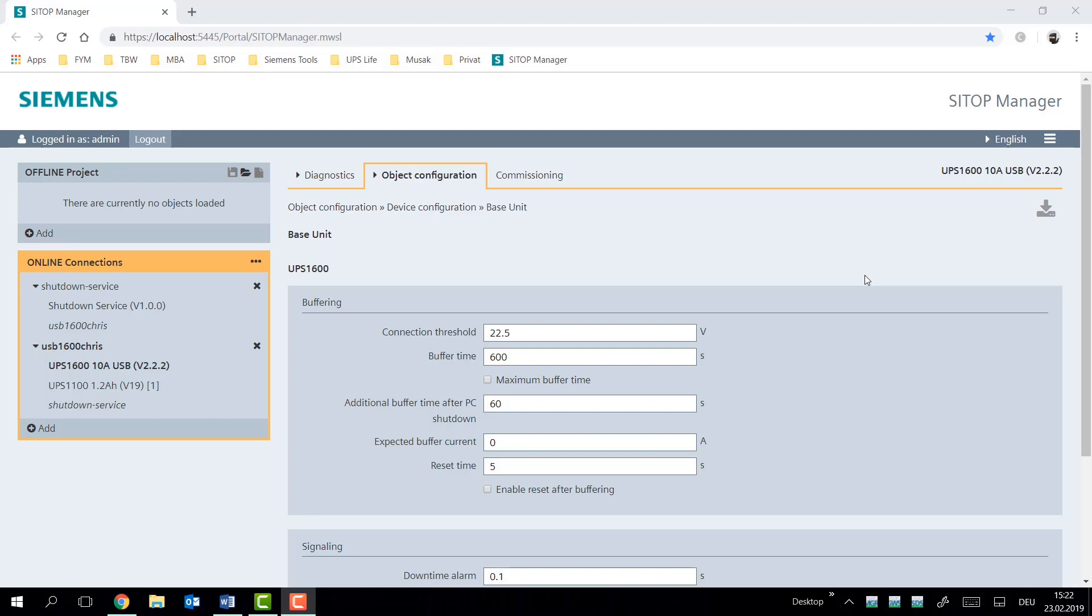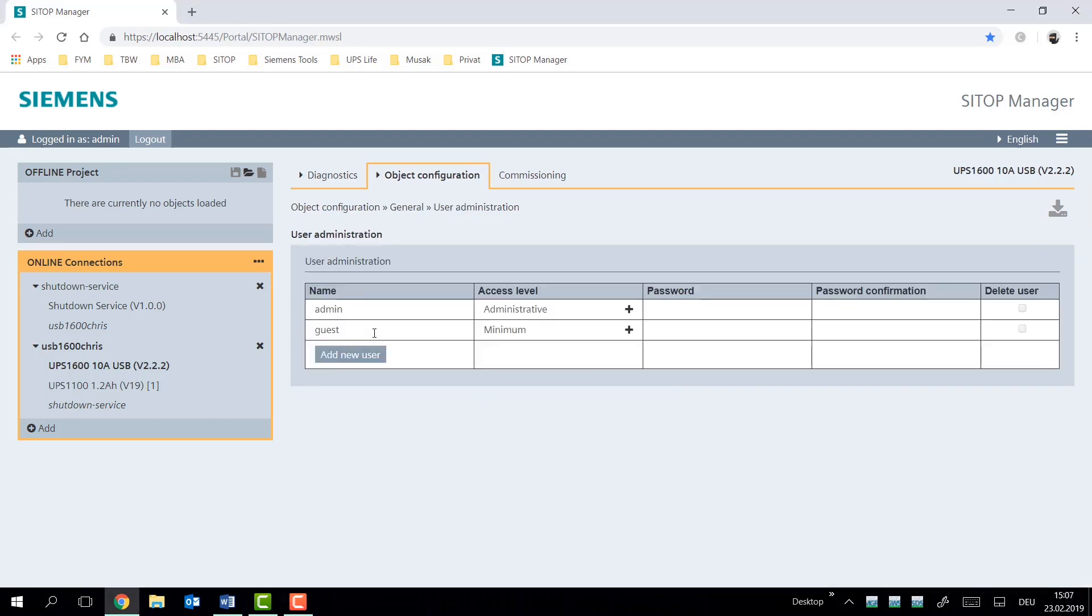The connection threshold here at 22.5 volts represents the minimum voltage allowed by the UPS1600 in your network. Any voltage variations above 22.5 volts will not be buffered. The moment that the voltage drops below 22.5 volts, a buffer event will be signaled and the UPS will switch to buffering mode of the UPS device.